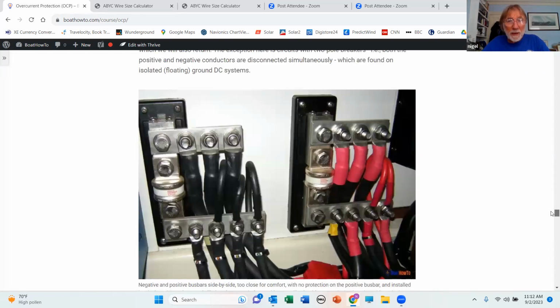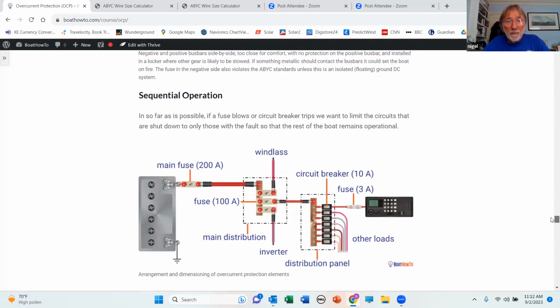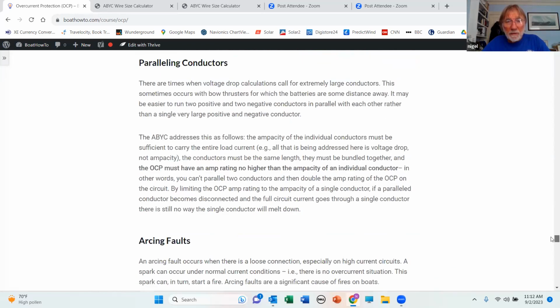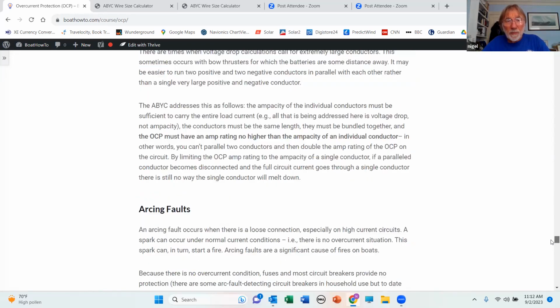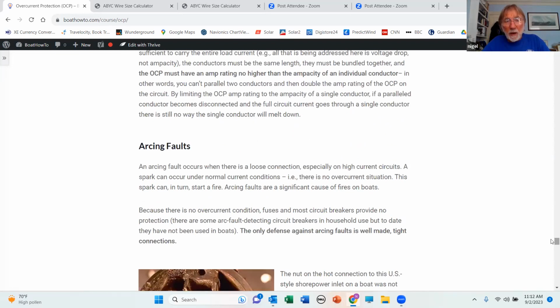I want to talk about something called arcing faults. The whole overcurrent protection approach is to deal with amp flows higher than the conductor can handle. So we're dealing with basically short circuits or partial shorts that put a sudden flood of amps through the conductor and overheat it. So the fuse or circuit breaker will protect against that.